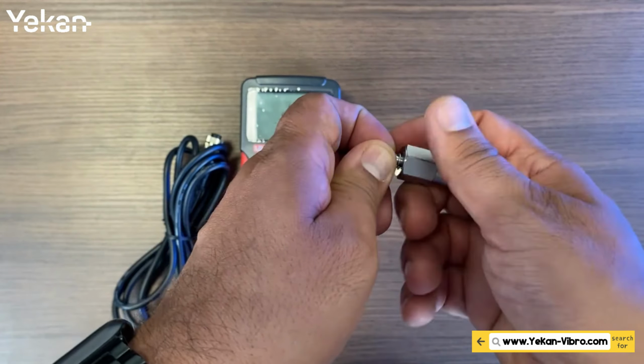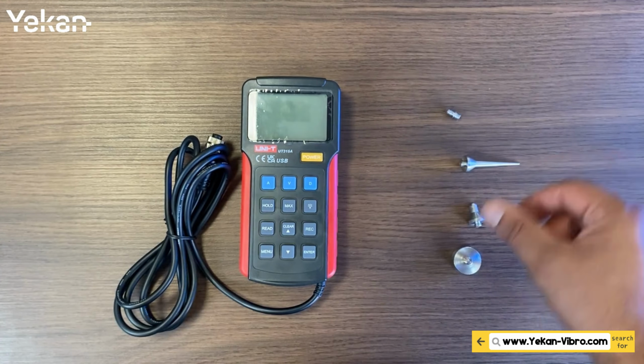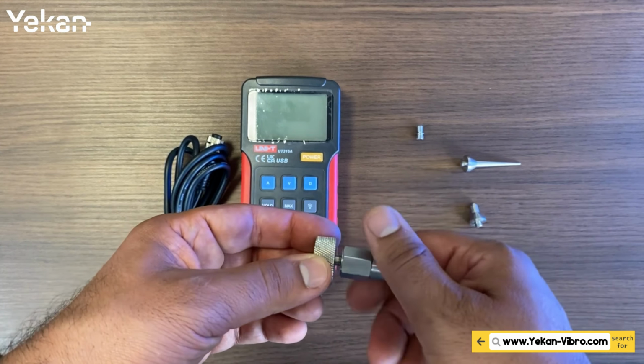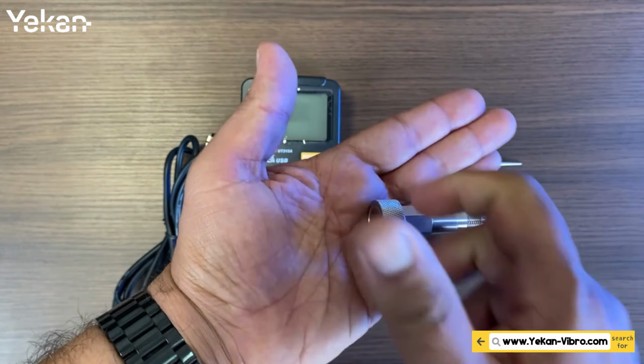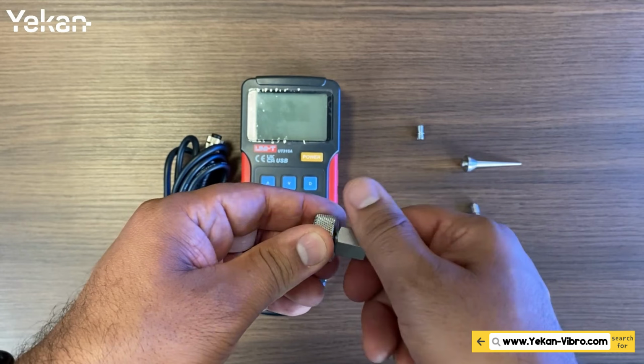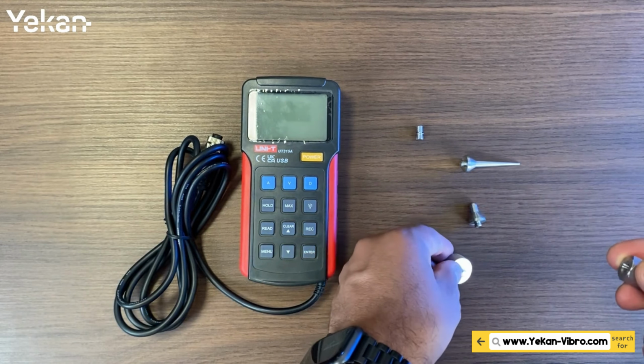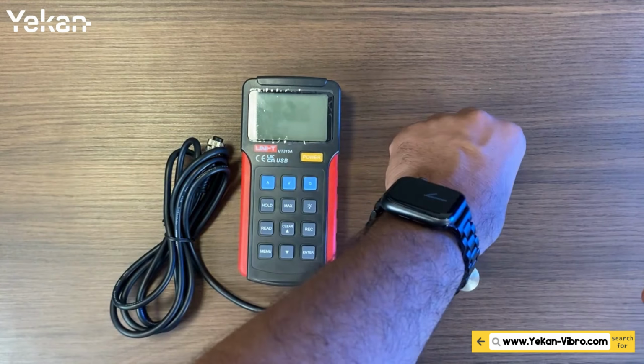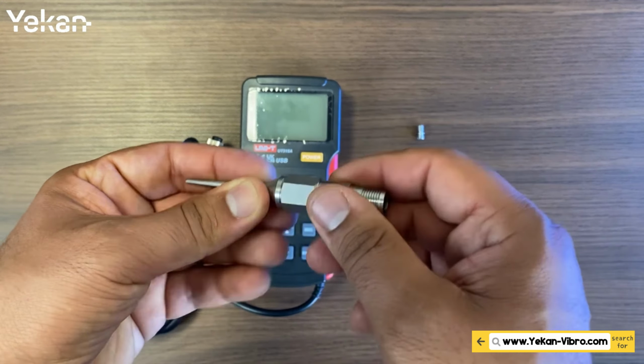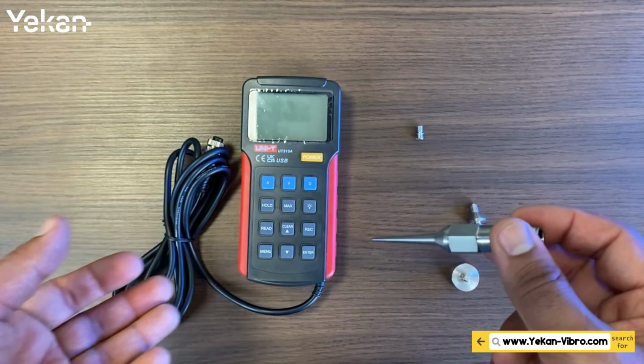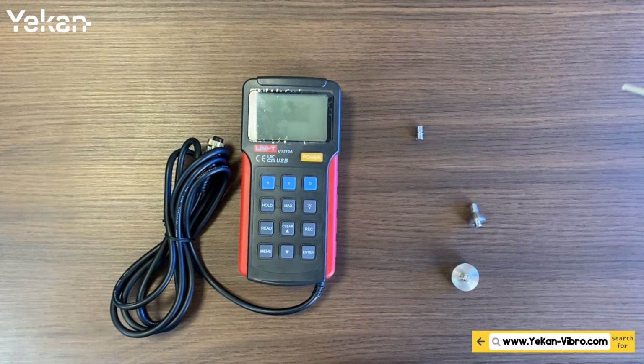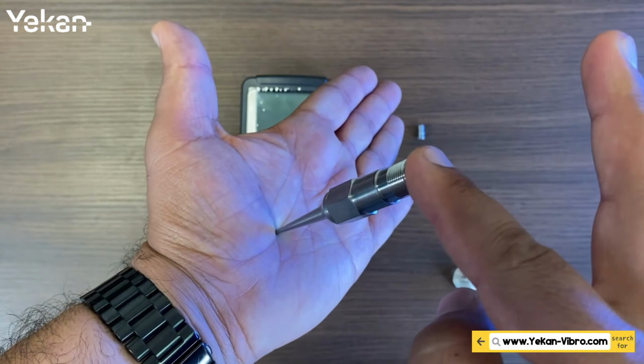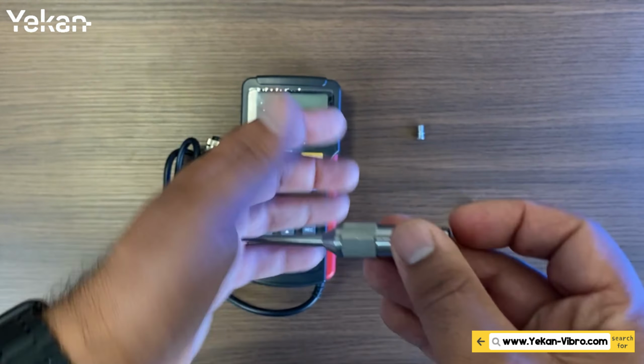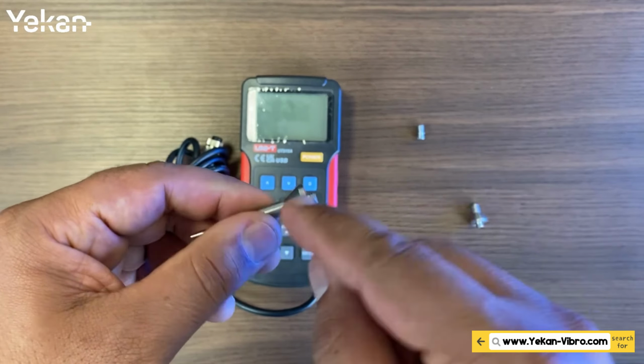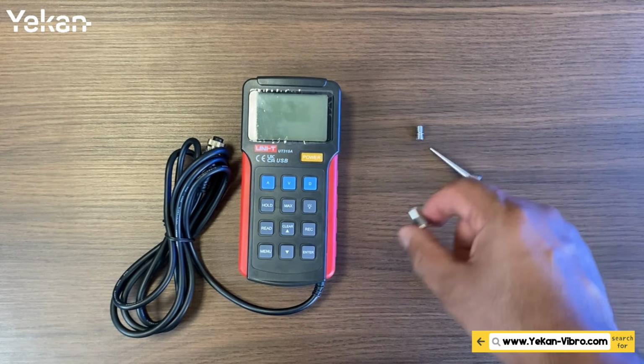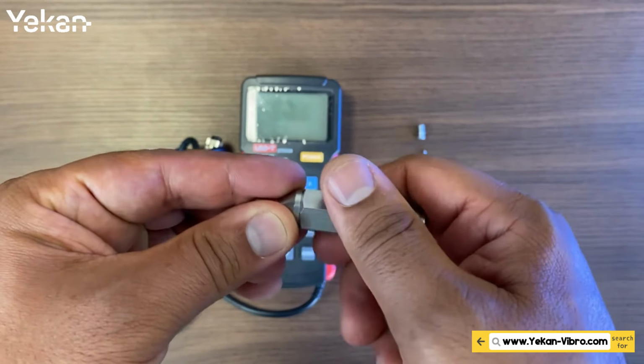Well, we open this screw. This screw is for permanent mount installation. We attach it to the magnet. You can connect this probe to it. And for places that are plastic, wooden, or aluminum where magnet cannot attach, with this probe you press and measure vibration. The longer the probe, at higher frequency it damps more and does not show. For that reason, small probes are also included.